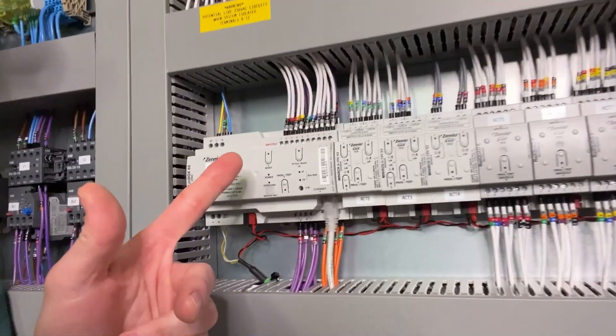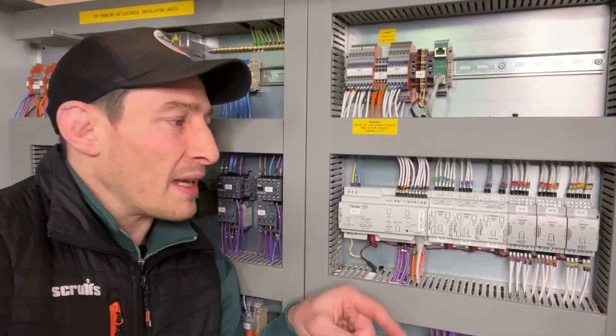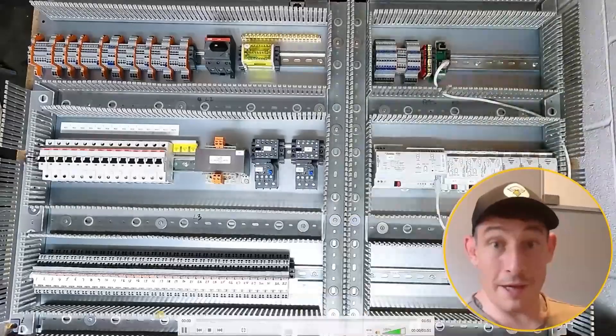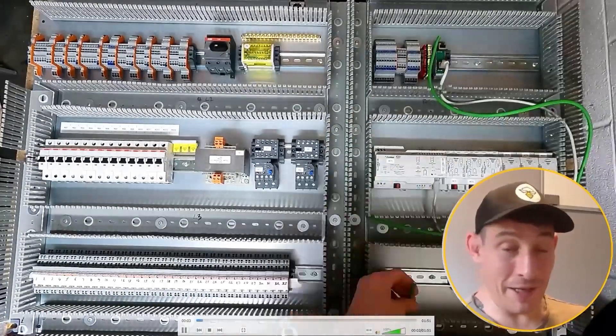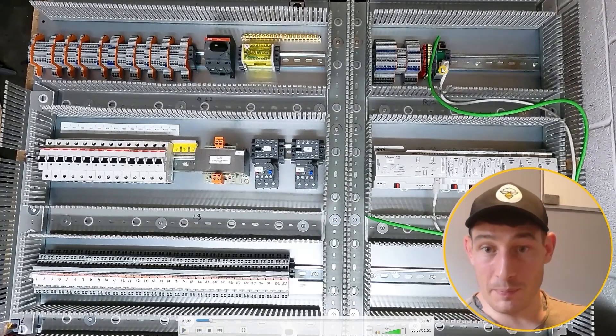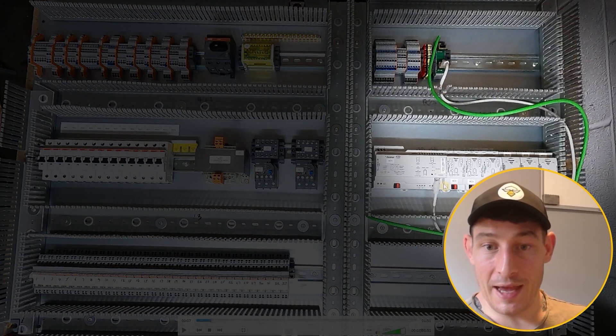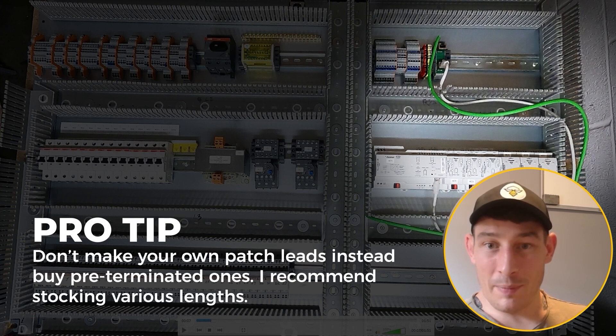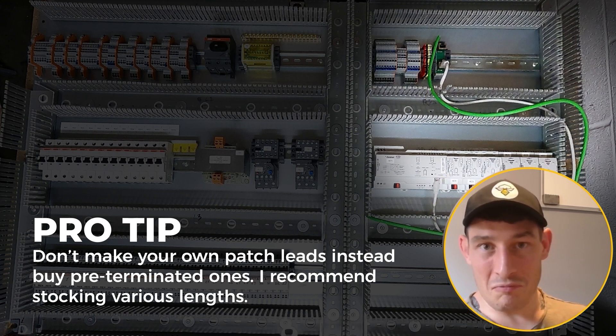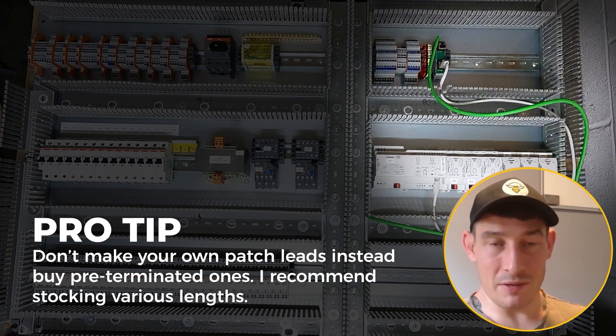These are PLC modules by Zennio on the KNX protocol, and I'm going to show you how I wired them within this real-world control panel. The first bit of cabling is the comms cable, and you can see the first bit is just getting that Ethernet patch lead in there. I wouldn't recommend making up your own patch leads from cat cable — just buy pre-terminated ones. Far quicker, far easier. Get a stock of various lengths and just use those.